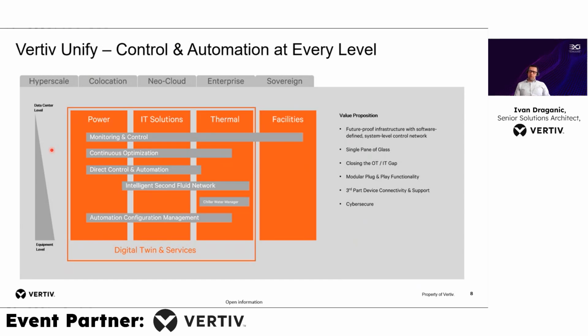From field level, where the monitoring equipment like power meters are on every type of box - and we're talking hundreds and hundreds, thousands of power meters - to power meters inside the switchgear for monitoring the UPS outgoing switches, the incoming breakers from the generators, from the utility. Everything is being monitored and displayed on a central Unify SCADA, which we also provide.